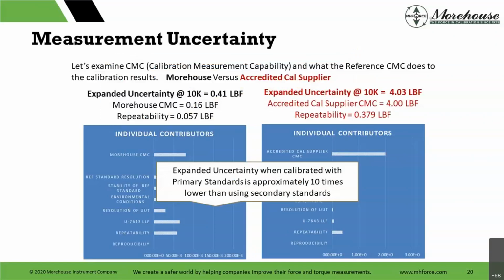So if we examine the capability and what a reference CMC does to the calibration results, Morehouse versus accredited supplier, we have here expanded uncertainty, same 10K load cell. We're operating with a CMC uncertainty parameter of 0.0016% of applied. Our repeatability here is about 0.057 because we know our uncertainty. The machine's plumb, level, square, rigid. We have really tight precision on the load cell, and then we can compare this with another supplier.